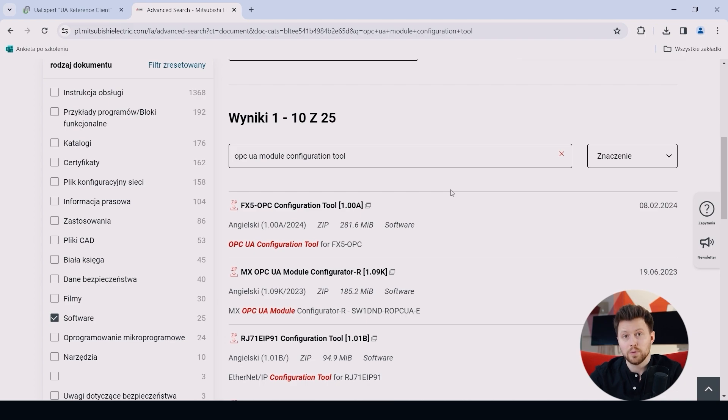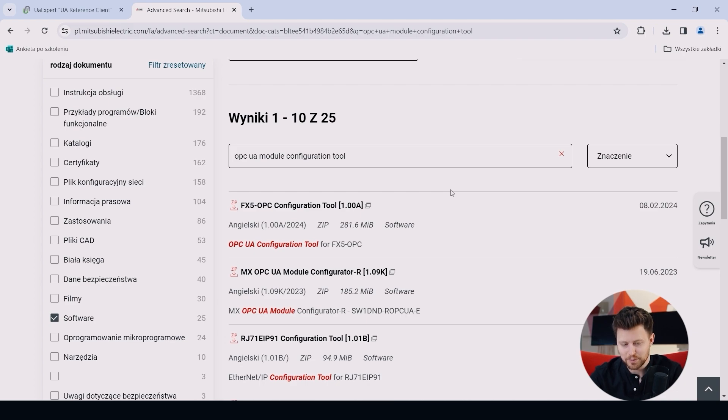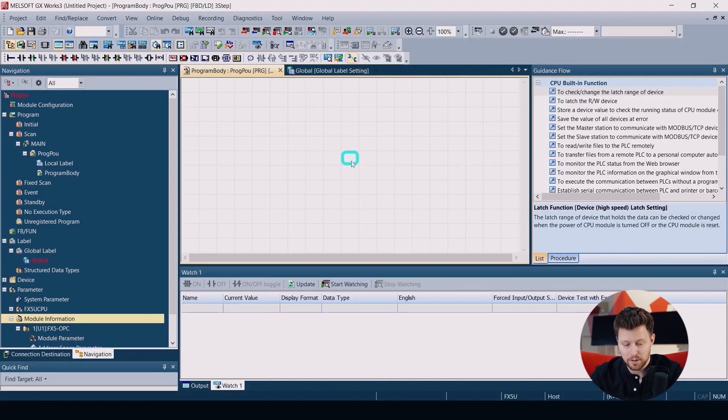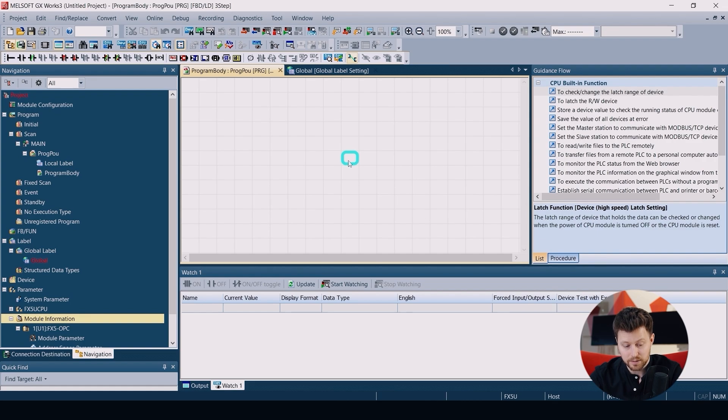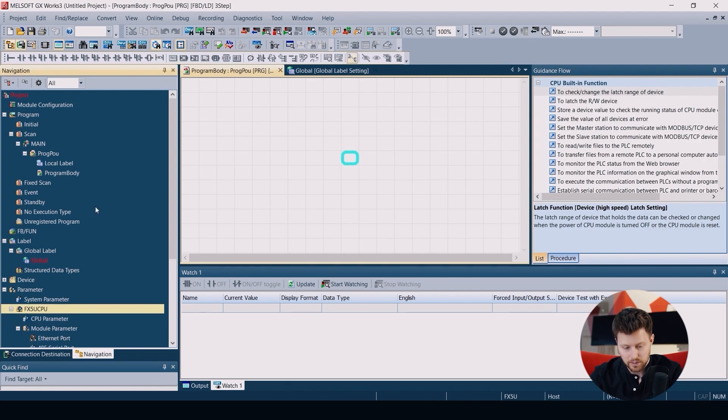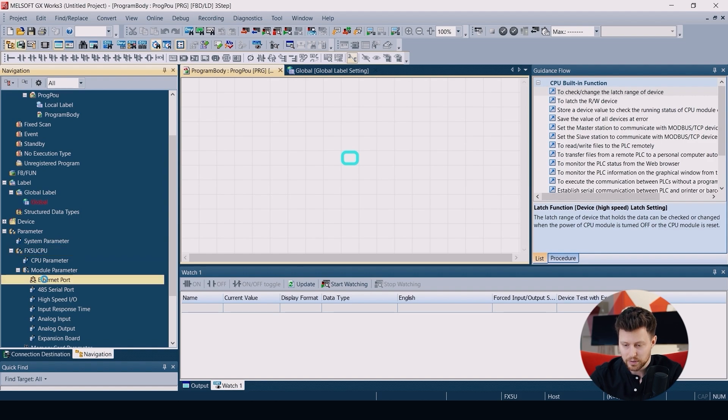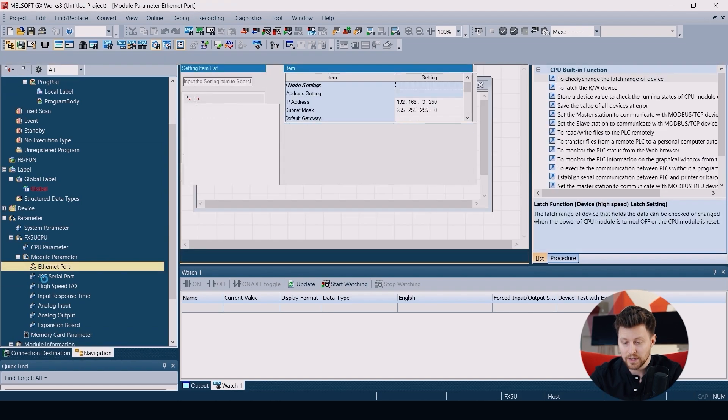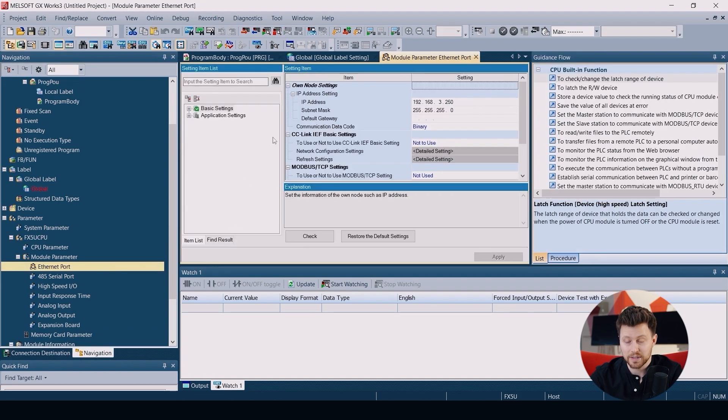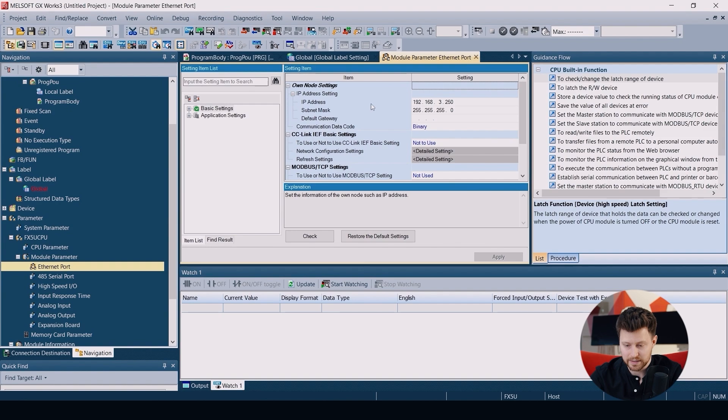And now when we have both of these applications, we can jump directly to GX Works 3 and start with configuring our PLC and our OPC module. So let's start with CPU itself. So in module parameter, we open the Ethernet port and here we have to set up the IP address and subnet mask.